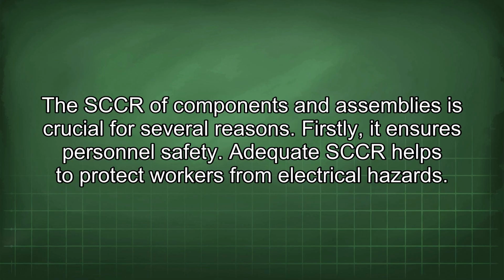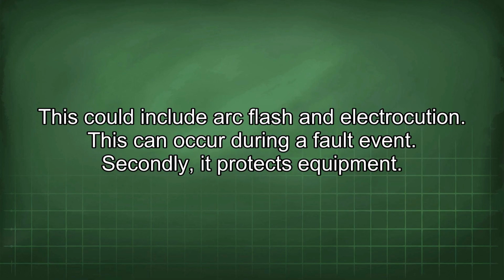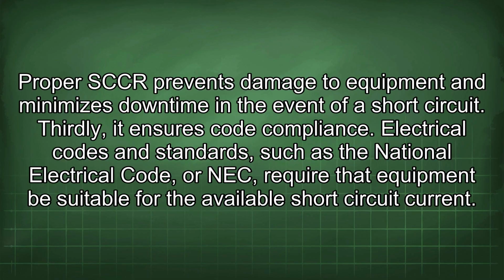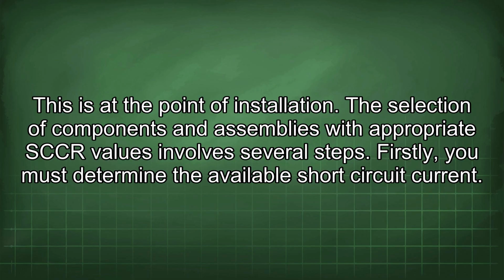The SCCR of components and assemblies is crucial for several reasons. Firstly, it ensures personnel safety. Adequate SCCR helps to protect workers from electrical hazards. This could include arc flash and electrocution, which can occur during a fault event. Secondly, it protects equipment. Proper SCCR prevents damage to equipment and minimizes downtime in the event of a short circuit. Thirdly, it ensures code compliance. Electrical codes and standards, such as the National Electrical Code, or NEC, require that equipment be suitable for the available short-circuit current at the point of installation.